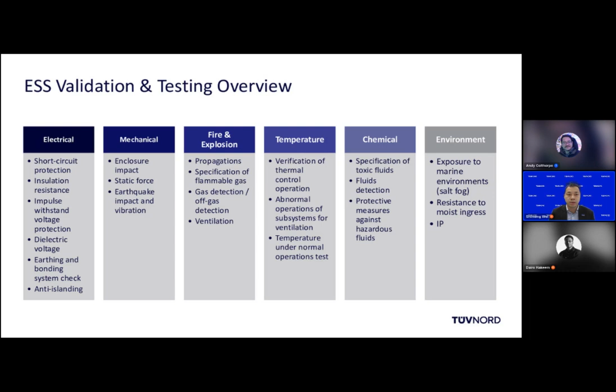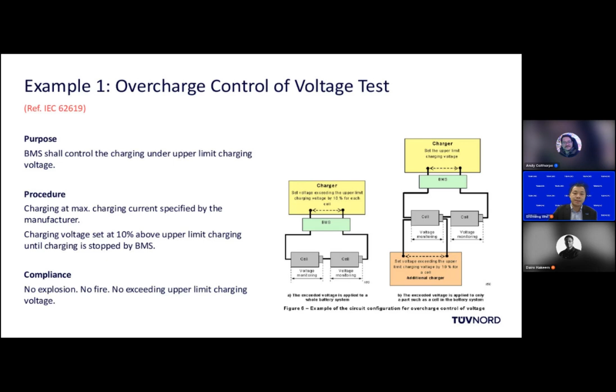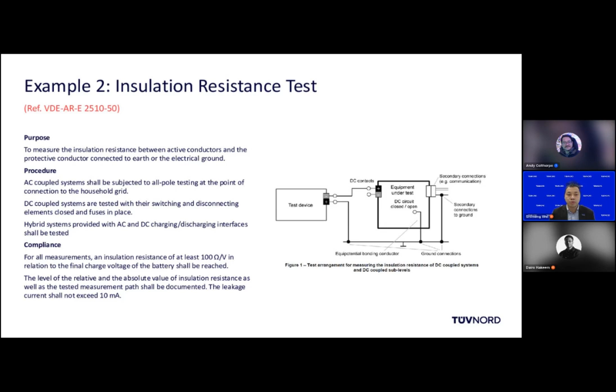Here are also some other examples I took out. For example, the overcharge control of the voltage test simulates that the control system in the battery, the BMS, is not functional and could cause an overcharge of the batteries and excessive voltage, and therefore could cause further explosion or fire. This is from IEC 62619. Another example, from the German standard VDE 2510-50, is the insulation resistance test, which simulates electrical shock that could cause hazards to people touching it.